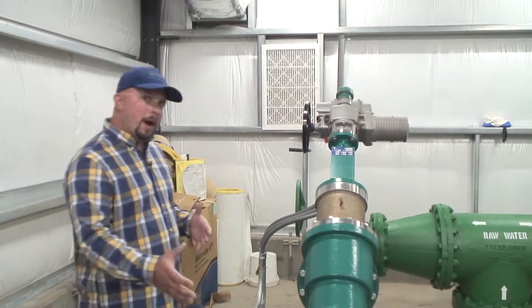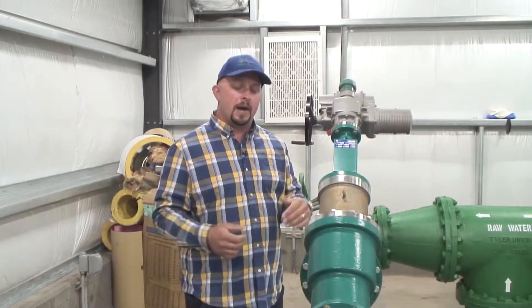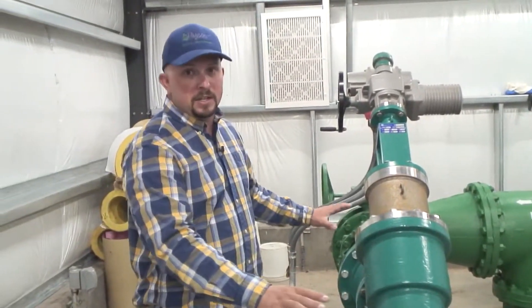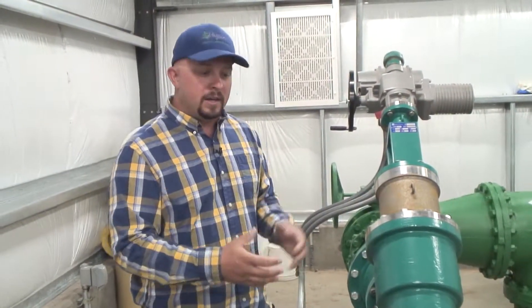This is our bypass Bailey valve. It not only acts as a secondary path for our water — since our hydro can only handle so much flow — it also picks up the slack so we can get our full amount of water needed to treat and serve the town. The internals of this valve safely remove the head of pressure within these chambers to prevent cavitation and pipe damage, because 200-plus psi can actually damage a pipeline if that pressure is not properly relieved.